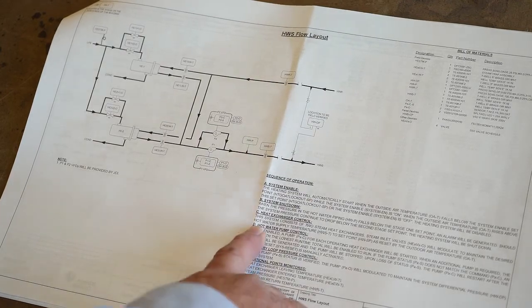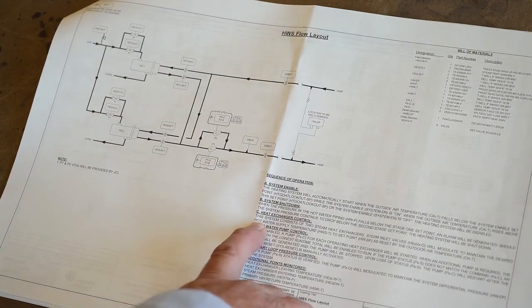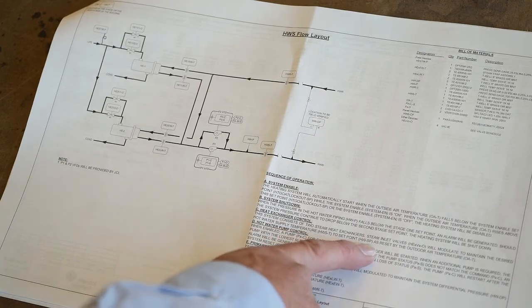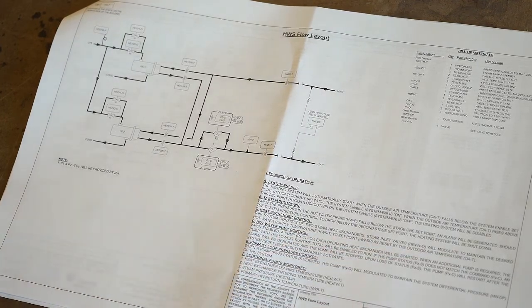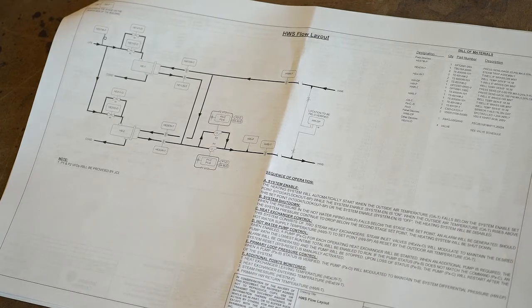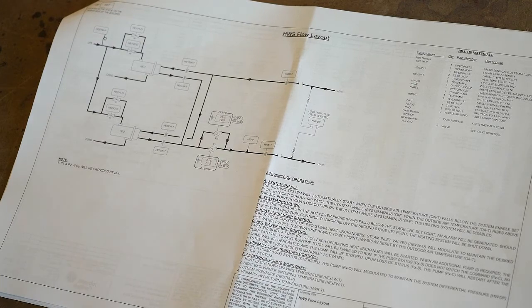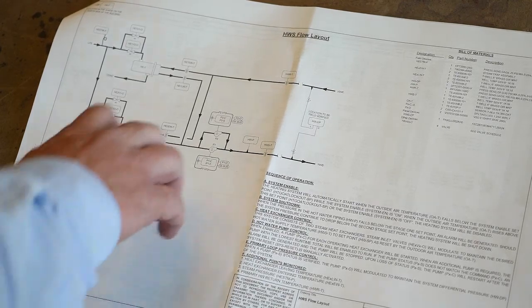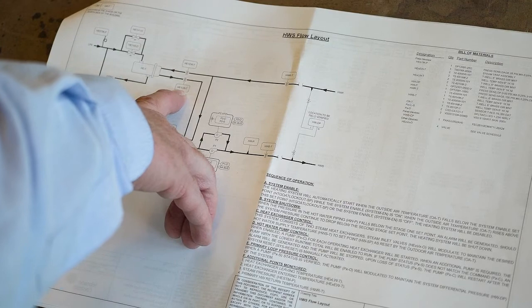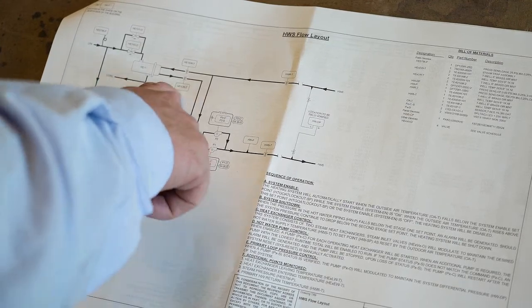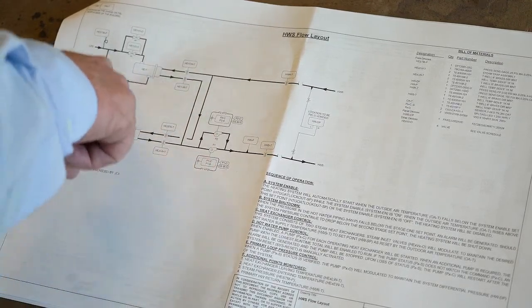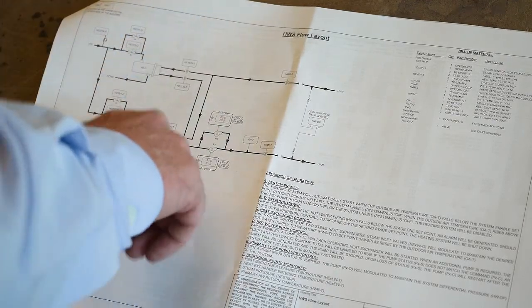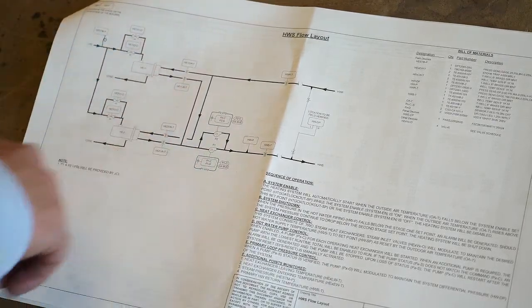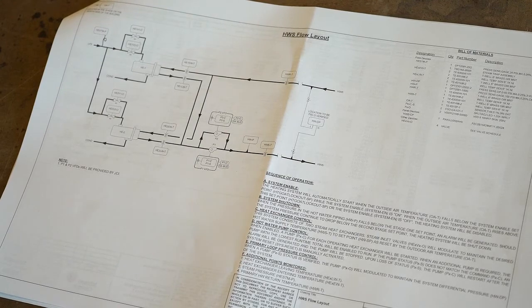I believe in here we're resetting it by outside air. So I know the top's 140, so the low's usually around 100. Okay. So we'll reset it between 100 and 140. Okay? And we'll do that off this heat exchanger hot water leaving water temperature. So those are the sensors that we use to modulate these valves. So if you get an error on these sensors, that's something that'll have to be addressed right away. Okay? These other two on the return side are for monitoring purposes.